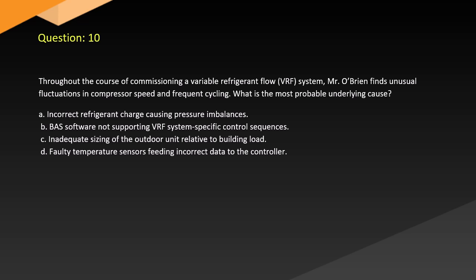Question 10. Throughout the course of commissioning a variable refrigerant flow (VRF) system, Mr. O'Brien finds unusual fluctuations in compressor speed and frequent cycling. What is the most probable underlying cause? A. Incorrect refrigerant charge causing pressure imbalances. B. BAS software not supporting VRF system-specific control sequences. C. Inadequate sizing of the outdoor unit relative to building load. D. Faulty temperature sensors feeding incorrect data to the controller.